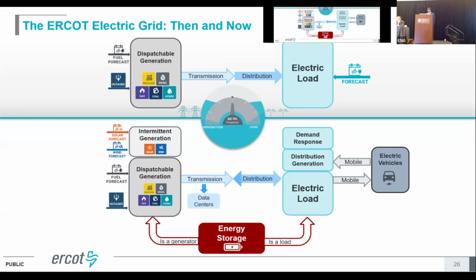A major improvement in the transmission area is the use of dynamic line ratings, where we look at the weather or temperature impact on the line's ability to carry flow, and then try to maximize that. ERCOT implemented this almost 10 years ago, so we've always had ambient adjusted ratings on most of our lines, which helped us maximize available transmission capacity.